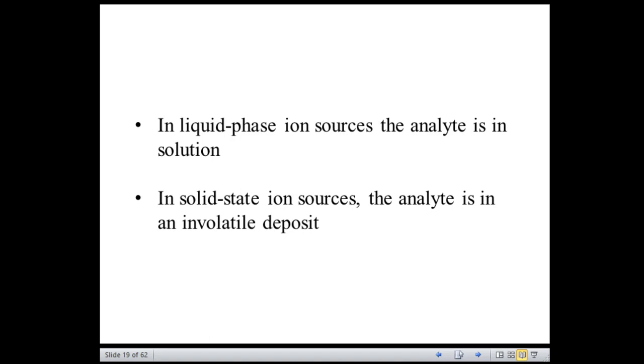Similarly, we see nebulization happening in the mass spectrometer sample introduction stage, where the droplets are introduced into the source, where the ions are produced at atmospheric pressure because they are thermally labile and do not have sufficient vapor pressure. These ions are then focused into the mass spectrometer through some vacuum pumping stages.